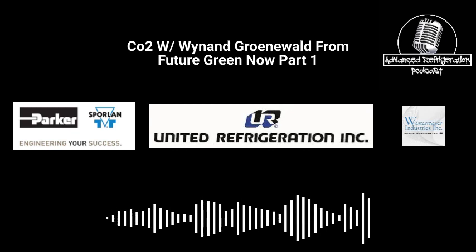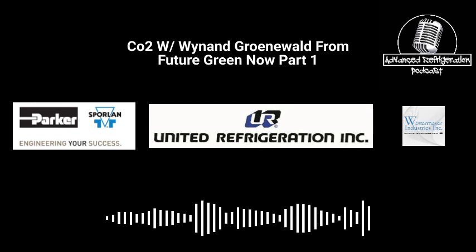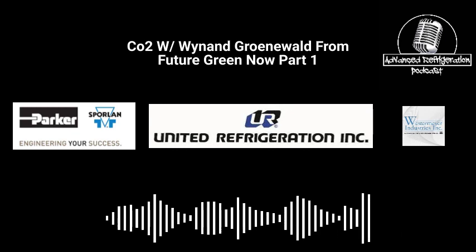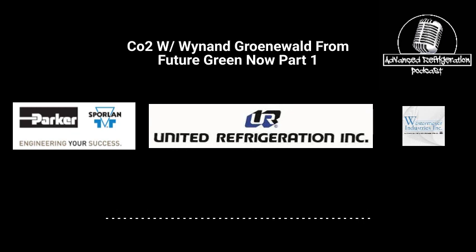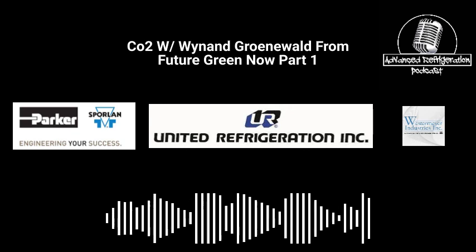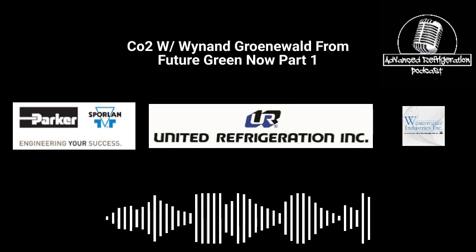Now, I was screwing around with a 326 one day, and I fat-fingered the max receiver set point, half a bar higher than I should have. I ended up knocking the top receiver up to like 550, 560. It opened up the flash bypass valve and basically loaded up the flash tank enough that it kept the medium temp running. It put enough load on the medium temp that it was able to build some discharge pressure and stay up. It wasn't the greatest discharge pressure, but it was enough to keep the rack running, and it was minus 10 outside with a 30-mile-an-hour wind.